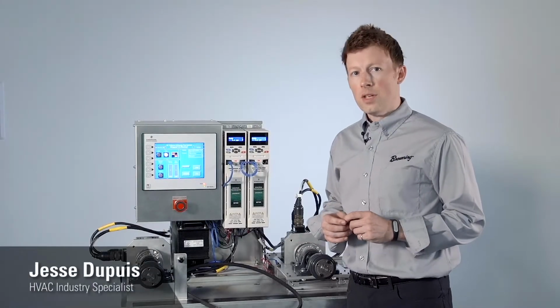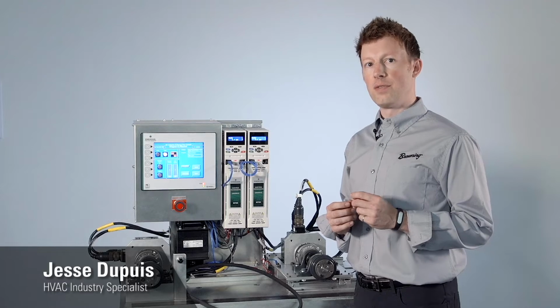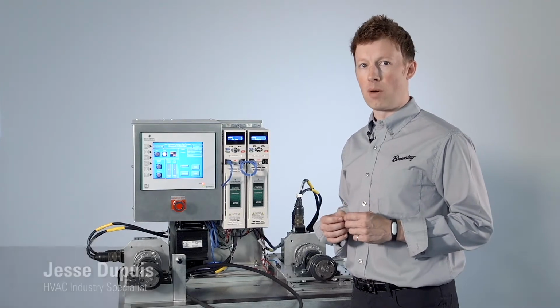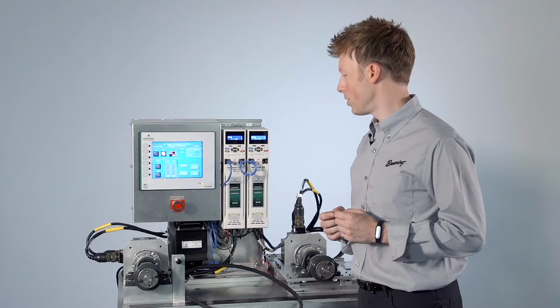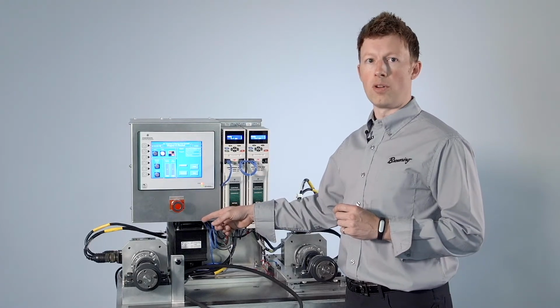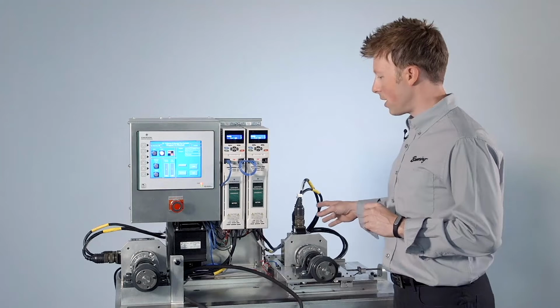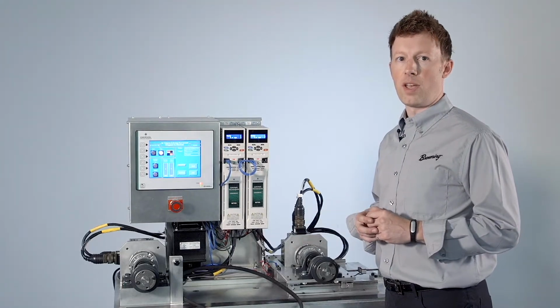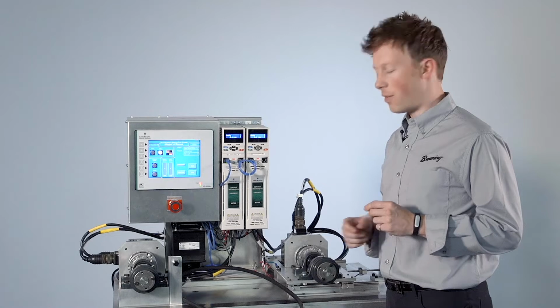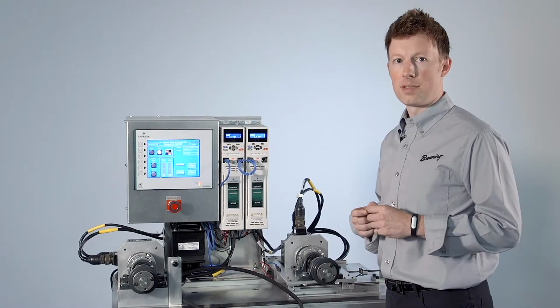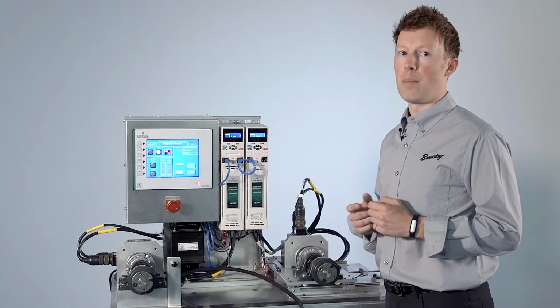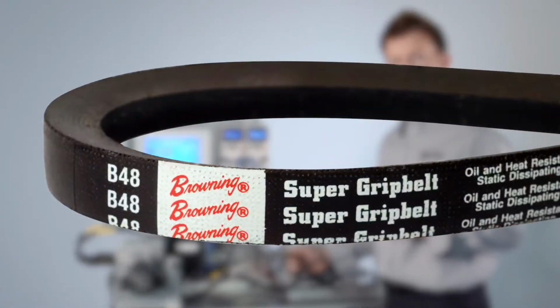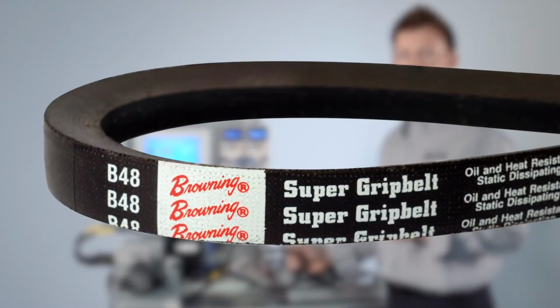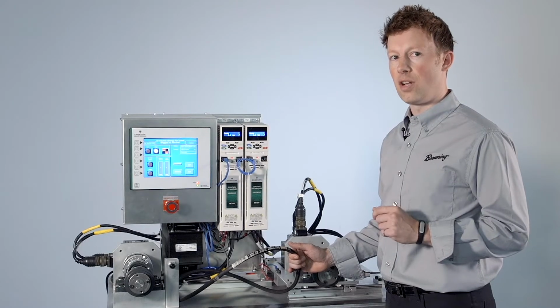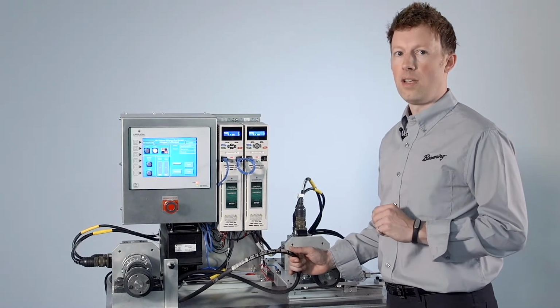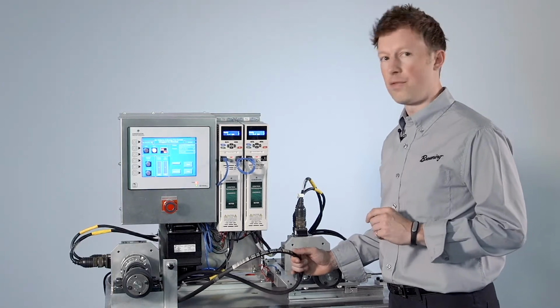Thanks, Don. So what we're demonstrating here is the effectiveness of different types of V-belts in their ability to transmit power from a motor to a fan in air handling applications. This is a 1 3/4 horsepower motor that we're using as a driver, and we're using the same size motor to simulate the loading conditions of a fan. And what we'll be comparing is the efficiency of wrapped belts as they compare to notch belts. Most commercial and industrial facilities use wrap belts, as the one seen here. These types of belts have a peak efficiency of 95%, but that's provided they're properly installed and maintained. However, most aren't, and you can end up seeing quite a reduction in the actual running efficiency.